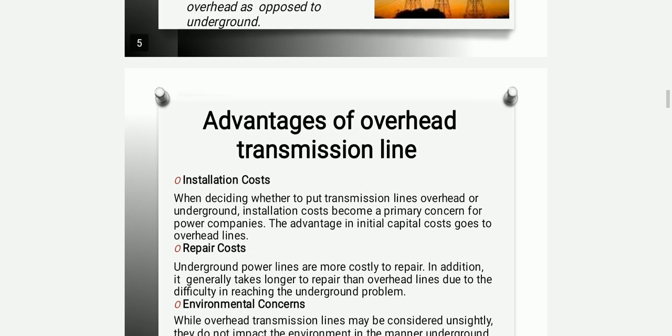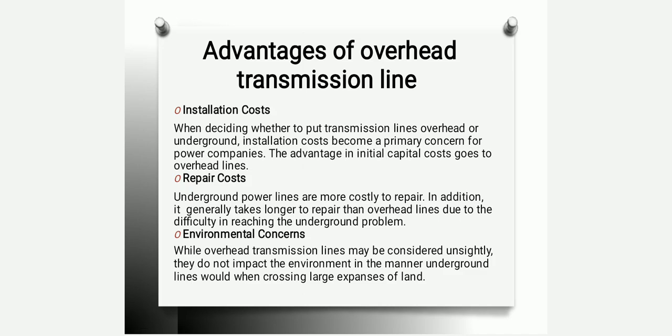The advantages of overhead transmission lines compared with underground transmission lines are: installation cost, repair cost, and environmental concern. For installation cost, the advantage in initial capital cost goes to overhead lines — it is more advantageous to lay an overhead line compared to an underground line. For repair, it is very difficult to find a fault in an underground line and repairing it may take much more time compared with overhead. For environmental concern, while overhead lines may be considered an eyesore, they do not impact the environment in the same manner as underground lines when crossing large expanses of land.